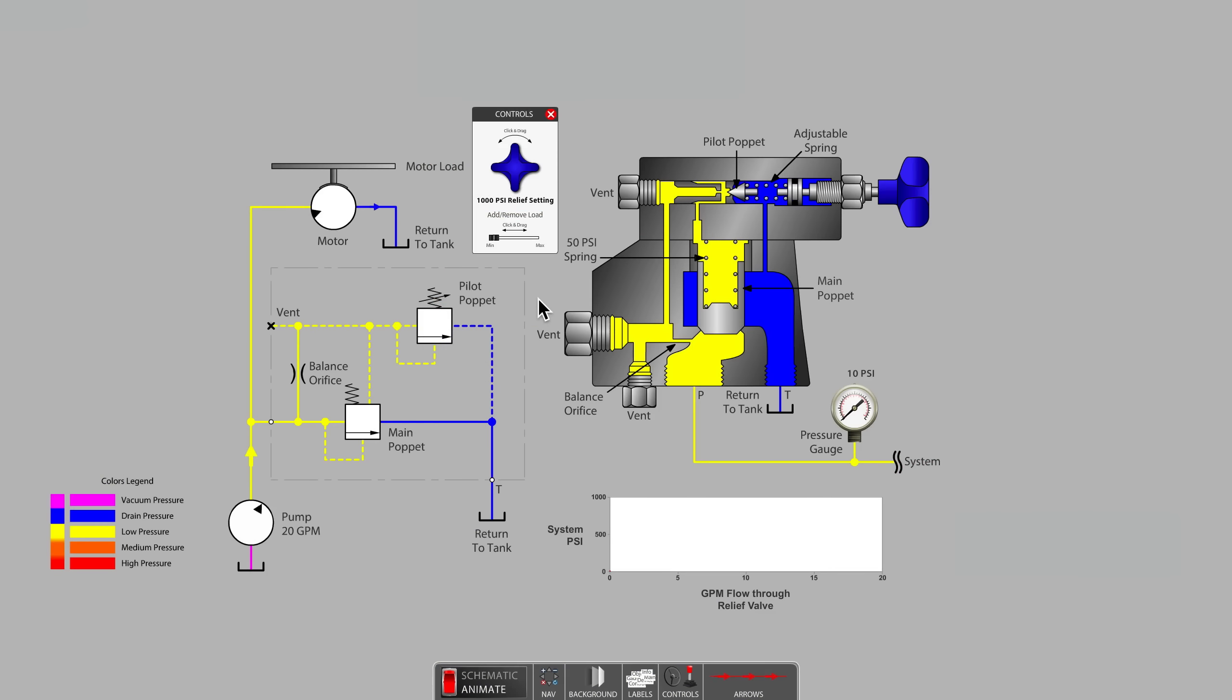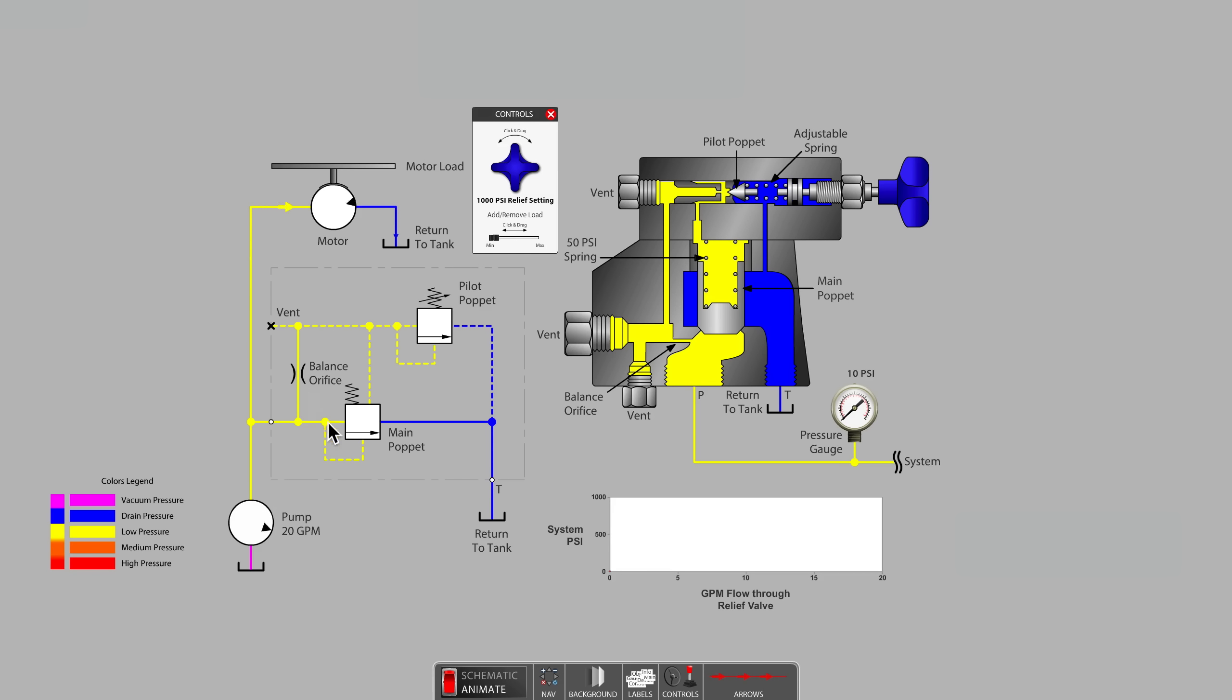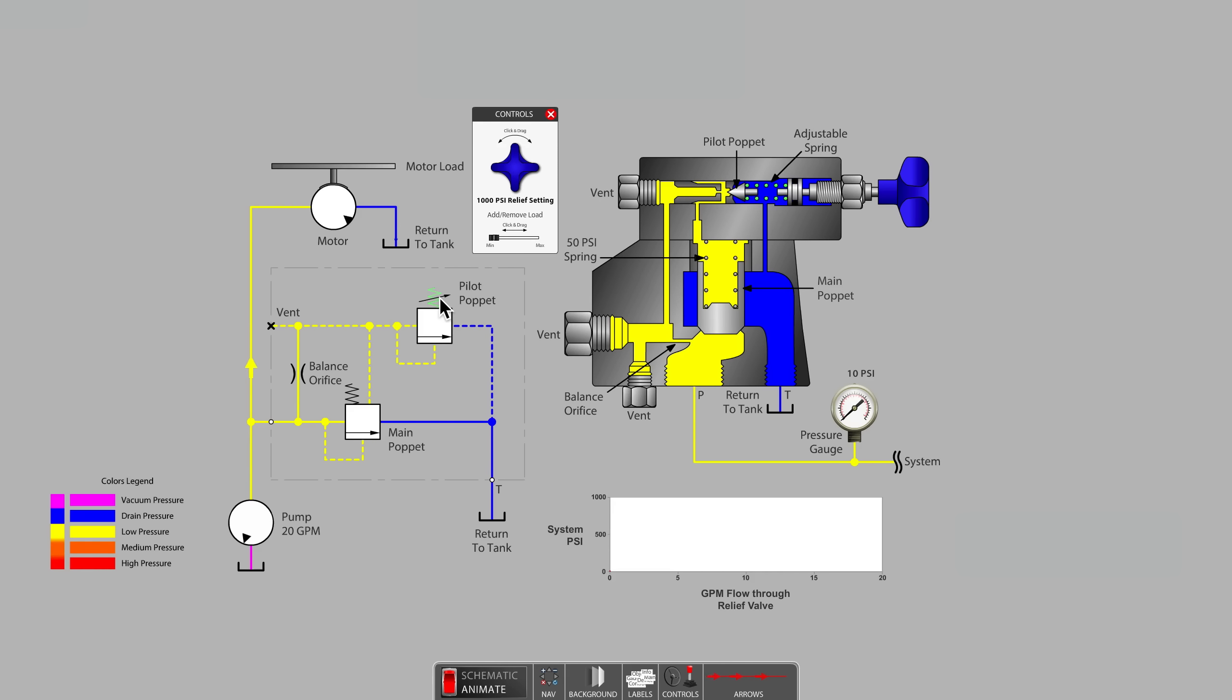This balanced style pilot-operated relief valve has, as you can see in both the symbol and the animated cutaway, two poppets and two springs. One of the two springs is adjustable, as indicated on the schematic symbol.